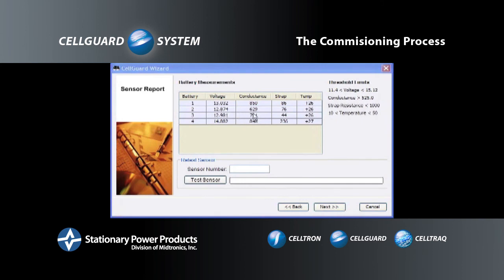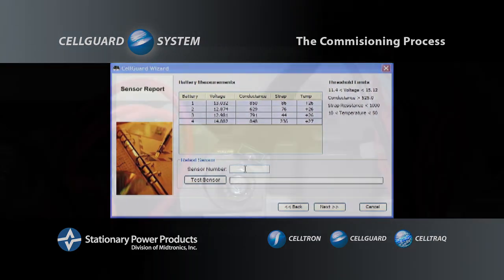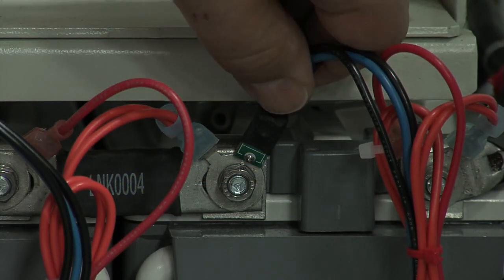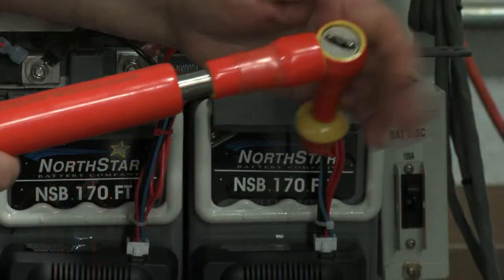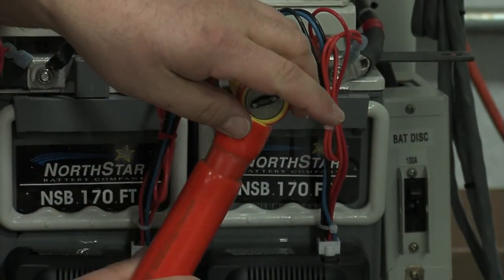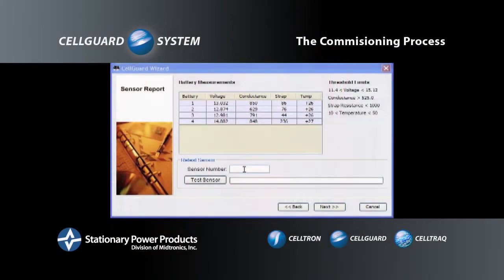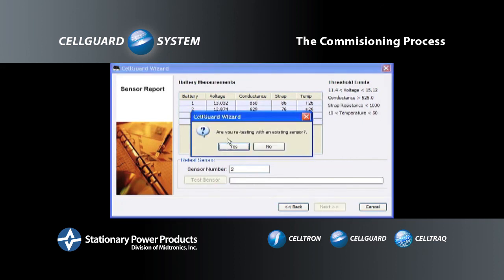The conductance for battery 2 is a little low in comparison to the other batteries. Check the connection from the cable to the battery, and also make sure that the battery hardware is properly torqued. Once this is verified or corrected, enter the sensor number that you want to retest and click Test Sensor. If you are retesting with the existing sensor, click Yes.